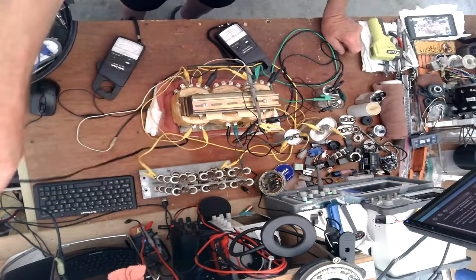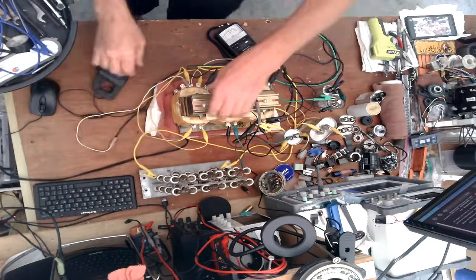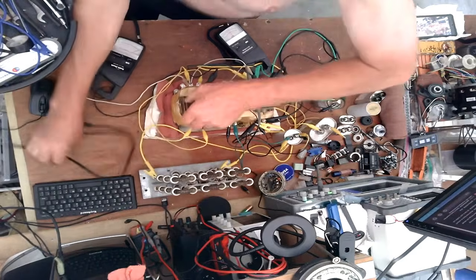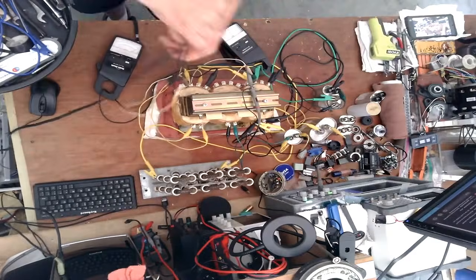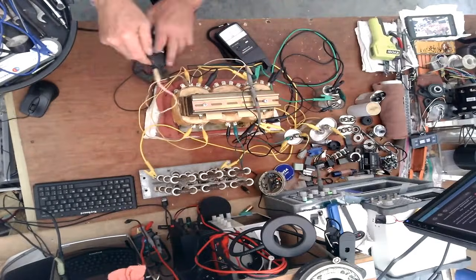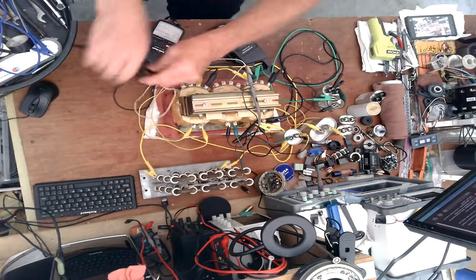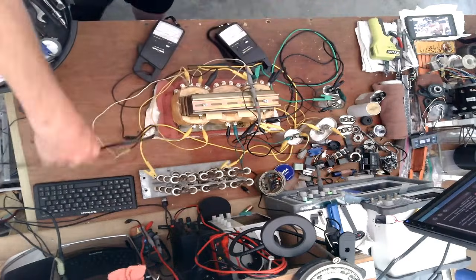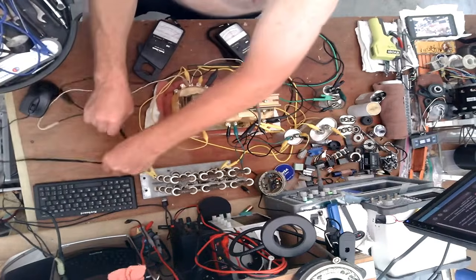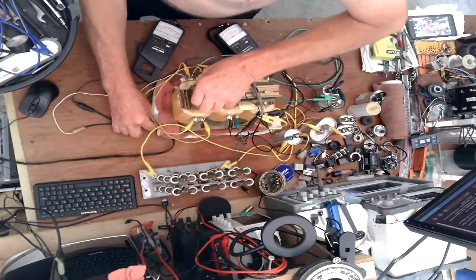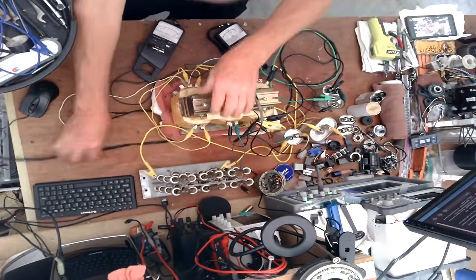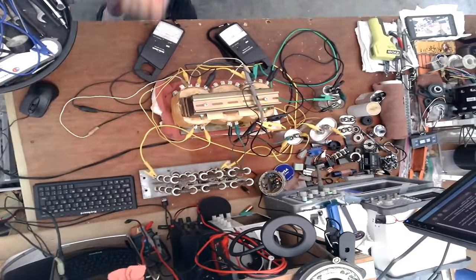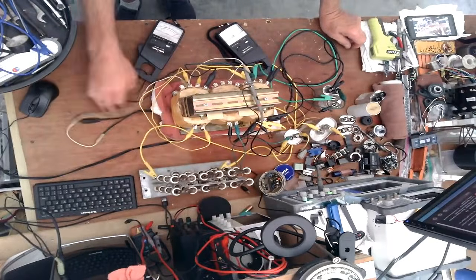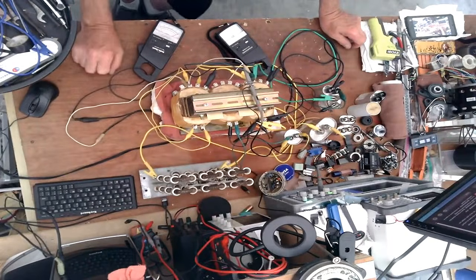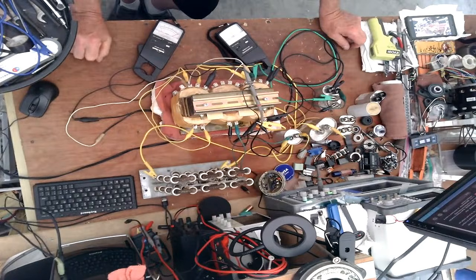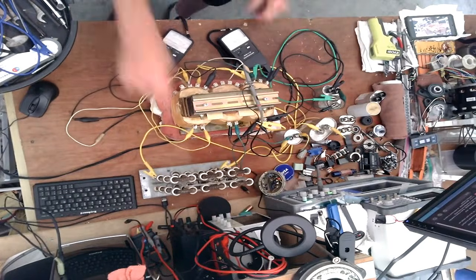This here is coming from the grid that goes underneath here. I'm actually going to pull this up so you can see that, and that's right here. So here's the white and the black. Black's going through the amp probe. I'm just putting it underneath this cord just a little to keep it from pulling down and pulling the alligator clips. So this is the grid coming in, that's the only thing coming in. Here's our load.